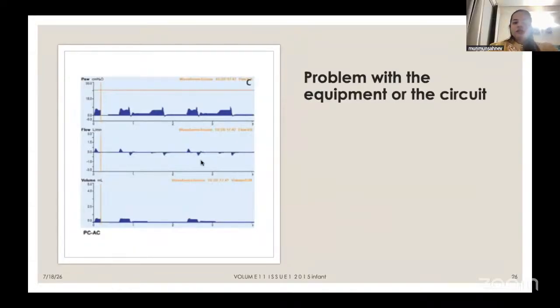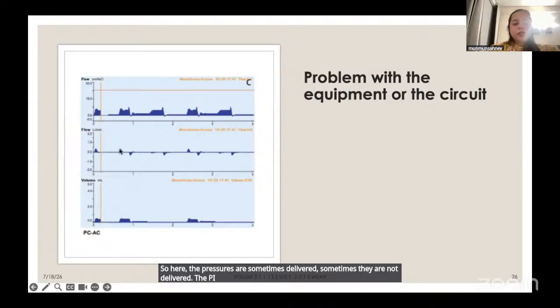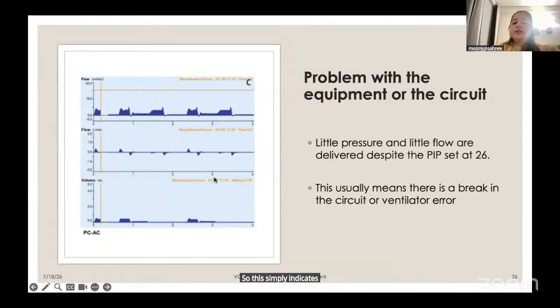So coming to the next graph. Here, if we see the pressure waveform, the flow waveform and the volume waveform are just going haywire. The pressures are sometimes delivered, sometimes they are not delivered. The PIP and the PEEP are not maintained. The inspiratory flow is not always followed by the expiratory flow, and we do not see any volume being delivered. So this simply indicates that there is a break in the circuit and you need to scan the circuit. Nothing is being delivered to the baby.